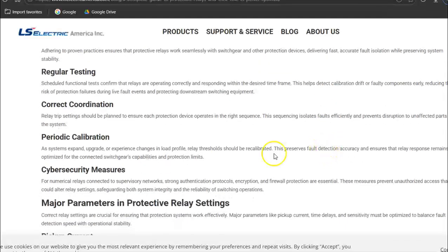So this is a good document. Note periodic calibration is in there. That's really important. These things have to be tested. There are crews that just go around and calibrate all of these. That is exactly what you are doing when you're doing Lab 11. Theoretically, you're going to put in known currents and test the trip time and compare it to a graph and say, does it pass or fail? We don't get quite that detailed, but that is the main idea. Correct coordination: trip settings should be planned to ensure each device operates in the right sequence. In other words, you want to isolate faults closest to the fault, not an entire area.